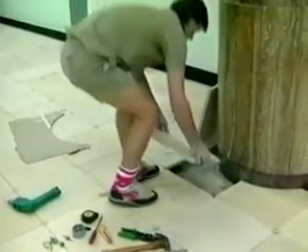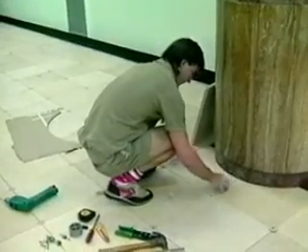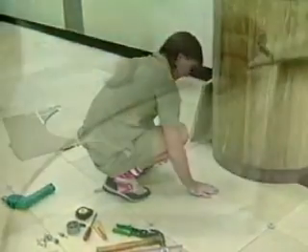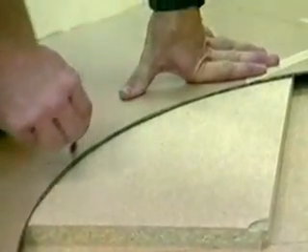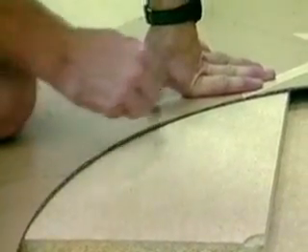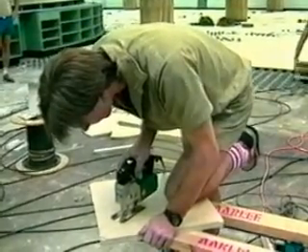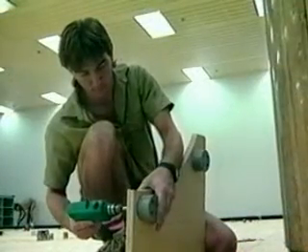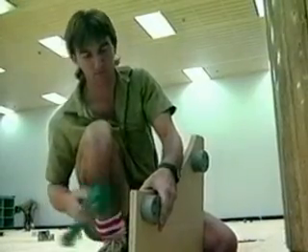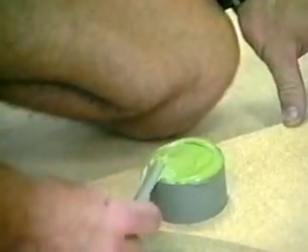The installer prepares infills around the perimeter of the floor and around any columns. The procedure is simple. Around a column, the panel is measured and the unneeded part is cut away. 2 freestanding cylinders are screwed to the underside of the panel, close to the 2 outer edge corners.